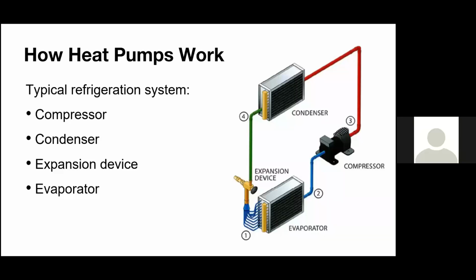Then we take that high pressure liquid inside, we expand it, bring it back to low pressure, then it evaporates, and that's where a lot of the cooling effect comes in. So that's what the expansion device shown here does. So essentially, depending on what way you're looking at it, these are either moving heat from the outside to the inside or the inside to the outside. In the next slide, we're going to show you two refrigeration cycles that are actually the same, but one of them is in cooling and one of them is in heating.